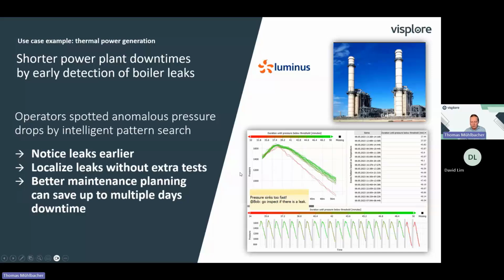And how do they do this? If you look at this picture here, you see they were looking at the rate of pressure drop during the shutdowns of the turbine. Okay, so when shutting down the turbine, that's a quite controlled time of operation. Looking only at these shutdowns, if the pressure is dropping then faster than usual, that's indicative of possible leak.